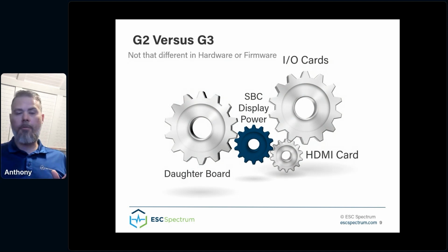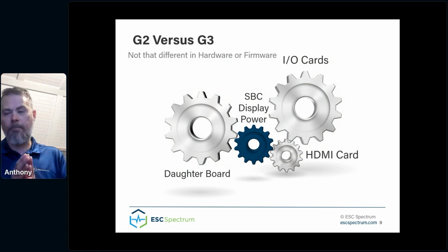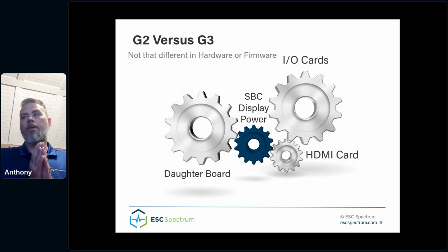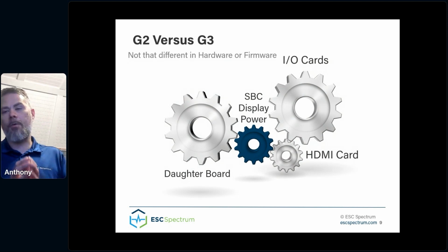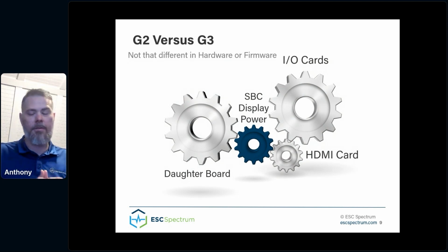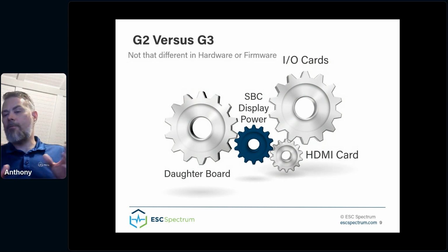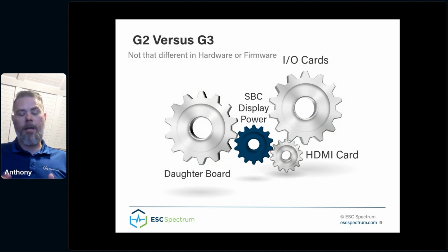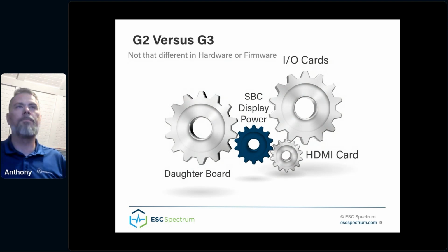There's some science behind this. There are thermal profiles for different parts on those boards, and they actually fail over time — in a way you don't know they've failed until you need them for protection, and then it's too late. You could end up with a situation where protection components cascade further through the system, which doesn't really fit within UL certification. Taking an old card and putting it into a new system violates the UL sticker on those boxes. That has to be handled at a production facility with UL audits taking place.